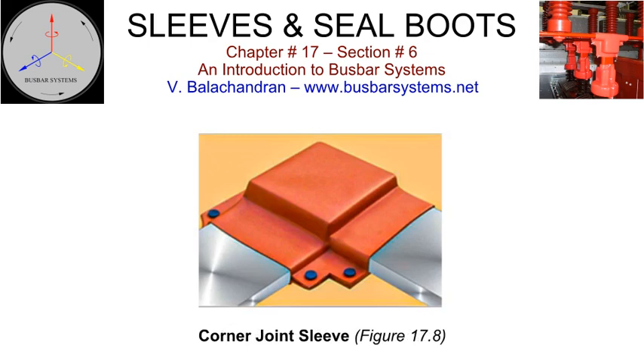Seal boots. An enclosed bus connection comprises several sections that are assembled at site. The conductors are bolted to form a continuous connection between the two ends. The joints can be broadly categorized as bolted joints, expansion/flexible joints, and end terminations. Each of these has specific bolting schedules, sizes, and shapes. Terminations interface with the customer's equipment. Consequently, the shape and size of the seal boot at each of these locations depends not only upon the joint but also upon the rated voltage.